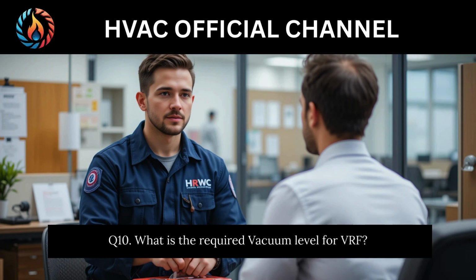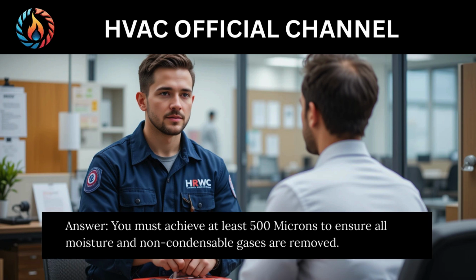Q10. What is the required vacuum level for VRF? Answer. You must achieve at least 500 microns to ensure all moisture and non-condensable gases are removed.